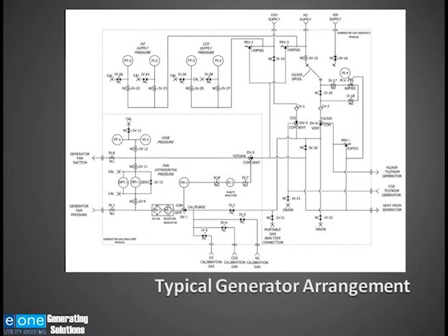And then as you follow the line down, you can see a flow meter, FM1, and then the purity analyzer. Under normal operation, the flow will come in through the fan pressure, go up through the analyzer, and then return to the fan suction. Now, if the generator is offline and you don't have a differential pressure, DV2 is opened and goes to vent, and that is used to create a small flow through the analyzer so that you can monitor the hydrogen purity even when you're on turning gear of the generator.